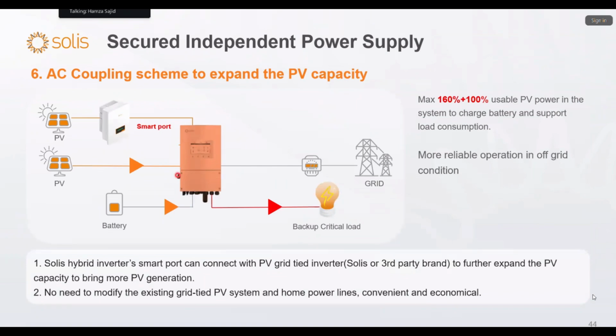AC coupling system. In the AC coupling system, it helps you expand the PV capacity. Actually, the customer already has an on-grid inverter available. Let's suppose 10 kilowatt, and this is also a 10 kilowatt on-grid hybrid inverter. So collectively, the customer has 16 kilowatt PV available, and he can charge the battery through this and support the critical load. So there is no need to modify the existing grid tie PV system and home power lines, which is convenient and economical. So you can save a lot of wiring cost and the solution charges.